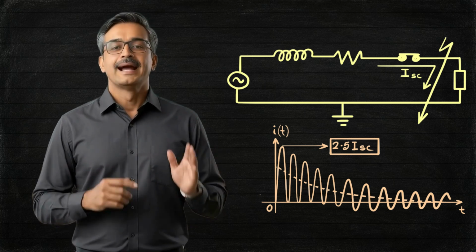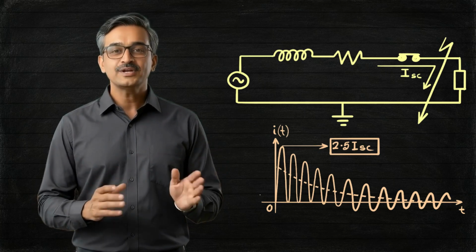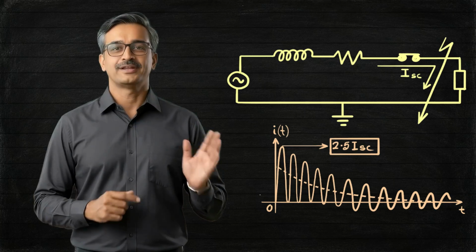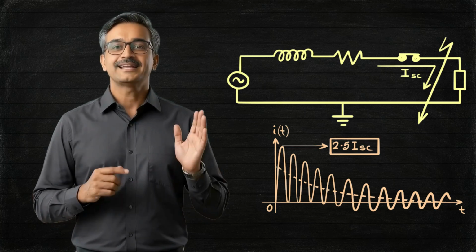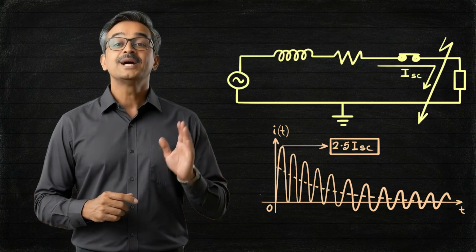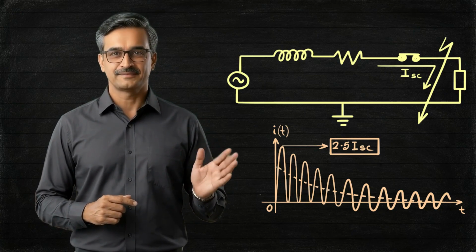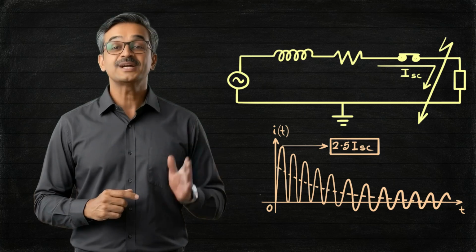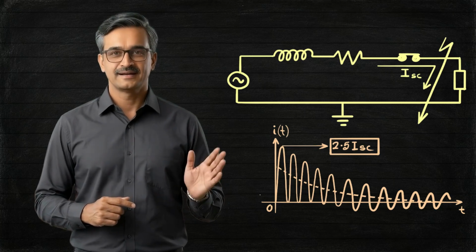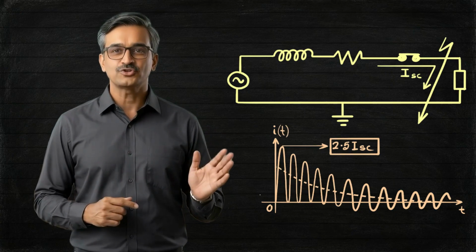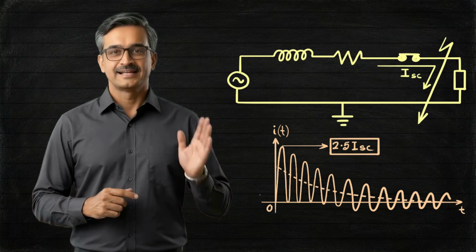Depending on the system reactance, this transient component decays very rapidly and is usually damped out within 2 or 3 cycles. As the transient component decays, the current gradually becomes the steady-state symmetrical short circuit current. In other words, although the transient component has disappeared, the short circuit itself still exists. Therefore, the steady-state short-circuit current continues to flow through the circuit breaker contacts.